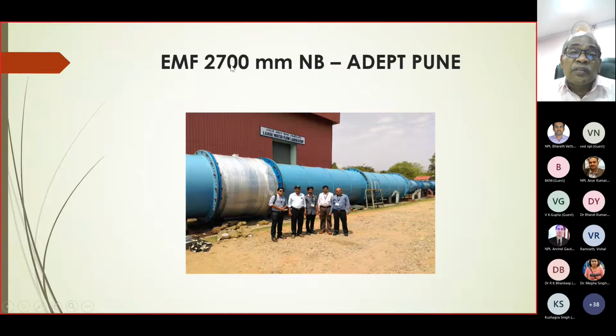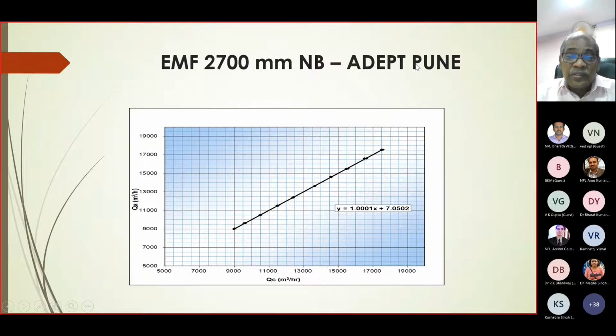This is the 2700 mm electromagnetic flow meter we have done for Adept Pune. See the calibration curve. Of course, I can admit one thing. This is 2700, so the velocity is also not 1 meter per second. In this 2700, the velocity is 0.79 meter per second. I have no other option.